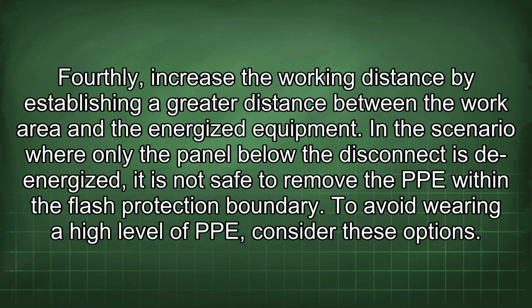Fourthly, increase the working distance by establishing a greater distance between the work area and the energized equipment. In a scenario where only the panel below the disconnect is de-energized, it is not safe to remove the PPE within the flash protection boundary.